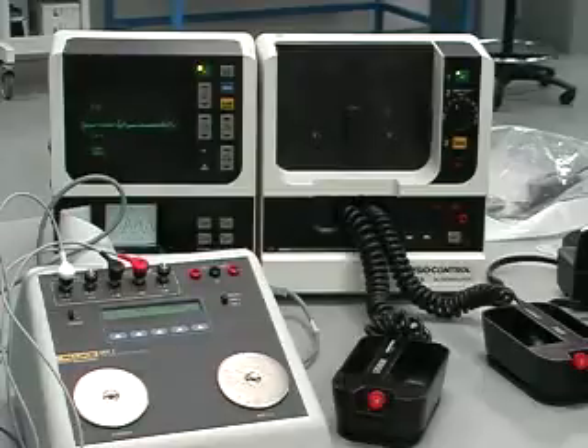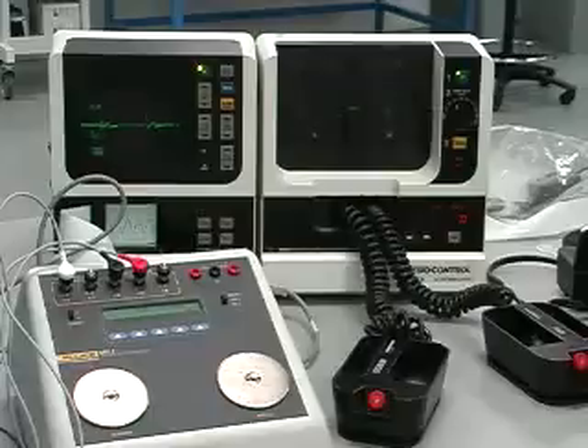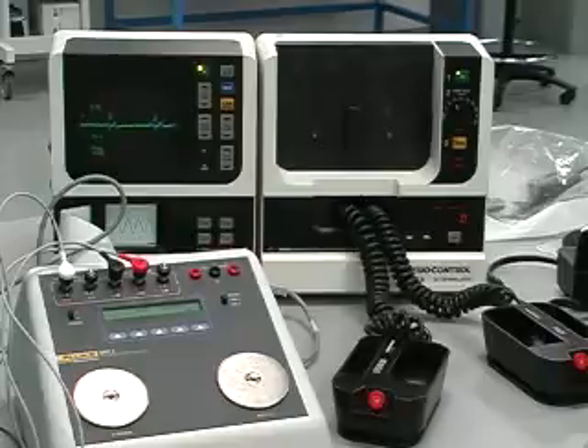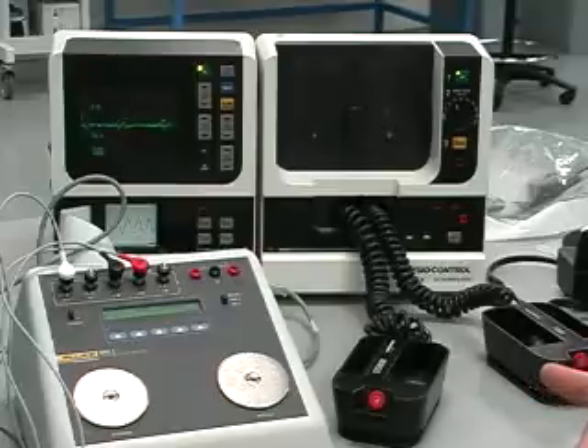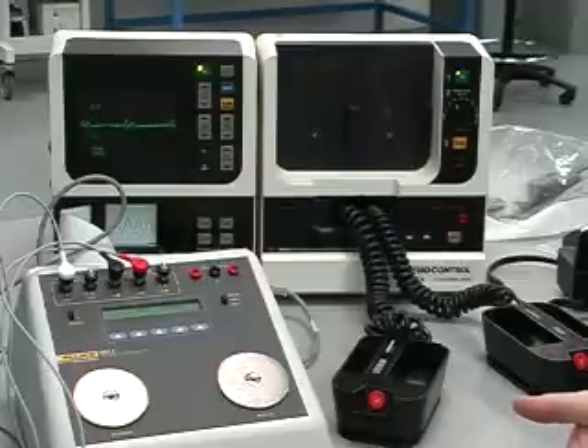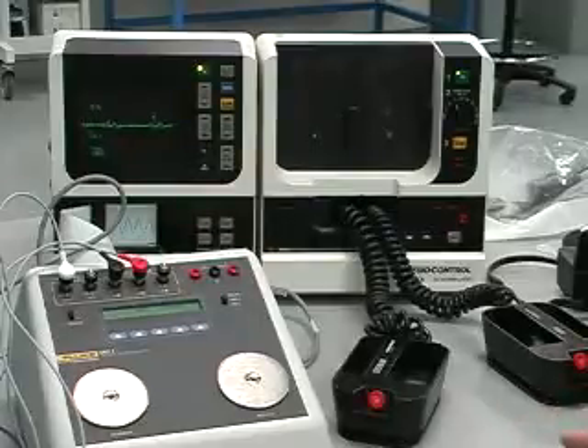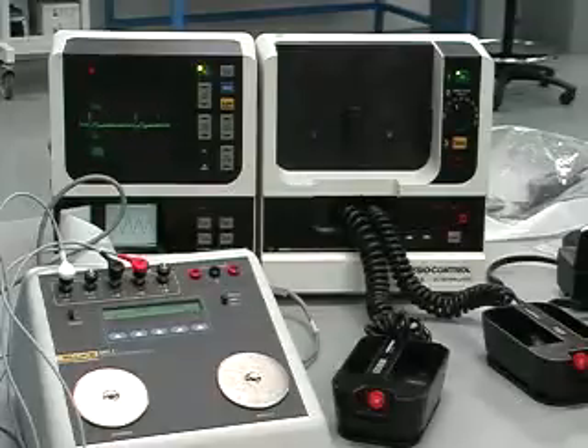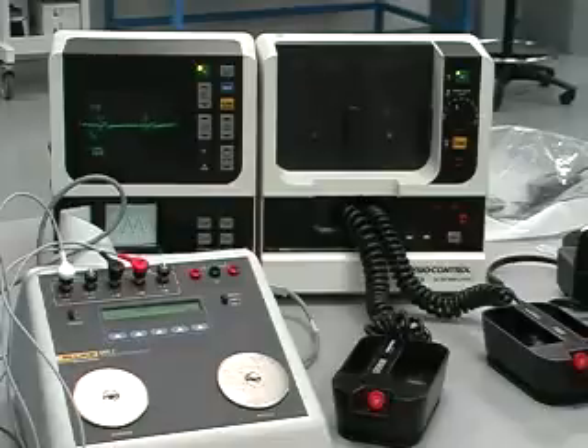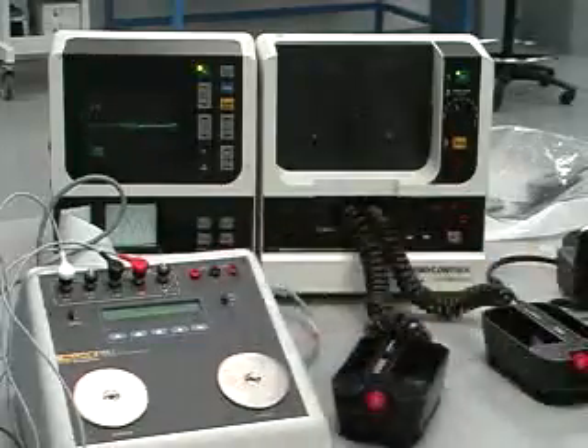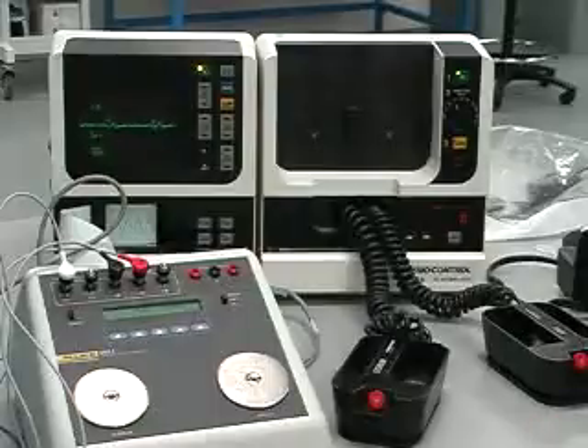Right, and it's best practice simply to have the defib and the monitoring all in one device. A lot of times they do use a slave off of a patient monitor. They use that for some other devices that need synchronization with the ECG signal, like an intra-aortic balloon pump assist system. They'll do the same thing. But with this, if they're going to run the test on me, I'd rather have the darn things tied together into one. But you can then use this higher level signal to accomplish that task. I've got it.